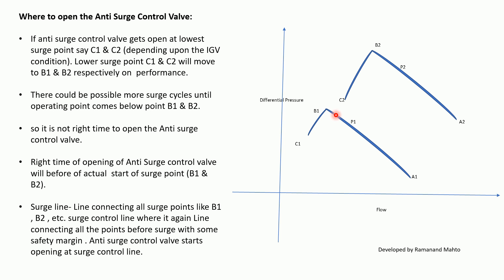Coming from C1 to below B1, or from C2 to below B2, takes some time, during which more surge cycles can occur — because that region is still the surge zone, not the safe zone. So opening the anti-surge control valve at the surge point itself is not the right time. The correct approach is to open the anti-surge control valve before the actual surge starts — that is, before reaching B1 and B2. Connecting B1, B2, and all corresponding points forms the surge line, and adding a safety margin to those points forms the surge control line.